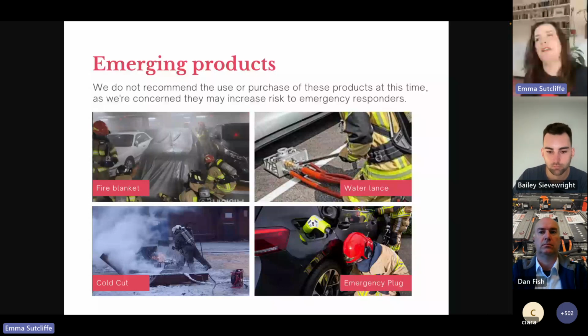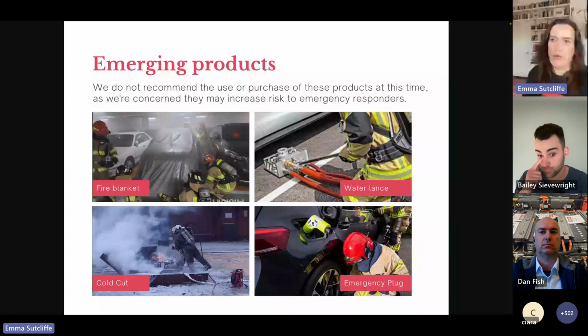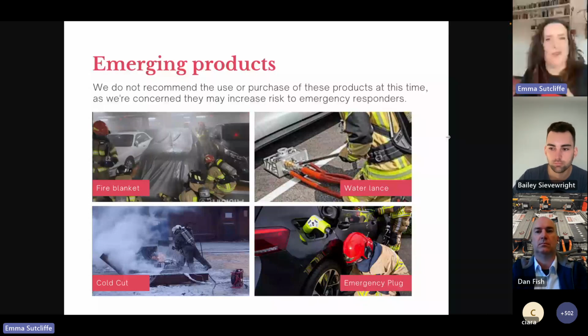If we take the example of a fire blanket, the point is to put it over an electric vehicle, and some manufacturers will use the word that it will extinguish an EV battery fire. It won't. It's not cooling anything underneath that blanket, so thermal runaway is still occurring under there and the gases are building up. In a couple of testing examples we've seen, someone's picked up a corner of that fire blanket, and the inrush of air has actually caused a vapor cloud explosion. So these are great, but we don't recommend at this time that anyone rushes out to buy these products, because we simply can't say with any confidence that this is going to decrease your risk.